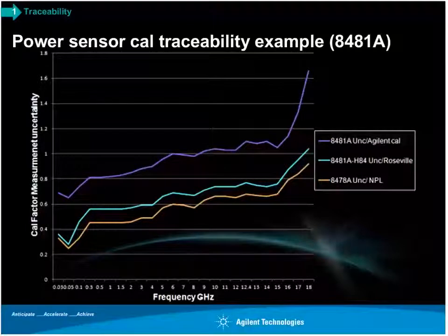Now, for that series of photos I just showed you, this is showing you the calibration factor measurement uncertainty. I think everyone knows that when you send a power sensor in, what they do is over the frequency range, they characterize how efficiently this power sensor converts power coming in to electrical signal and then to an indicated reading. So the uncertainty is obviously how accurate is that conversion, and you see 3 lines here. The lowest line in yellow is an actual one for an 8478 thermistor power sensor that was provided by the National Physics Lab, again from the UK.